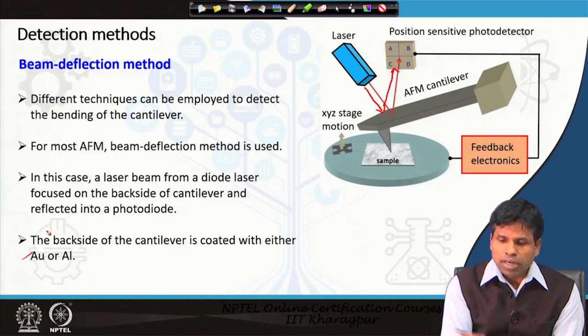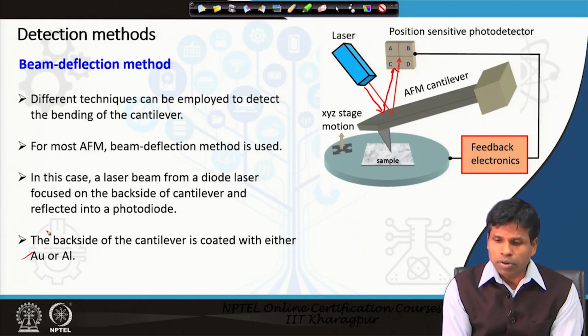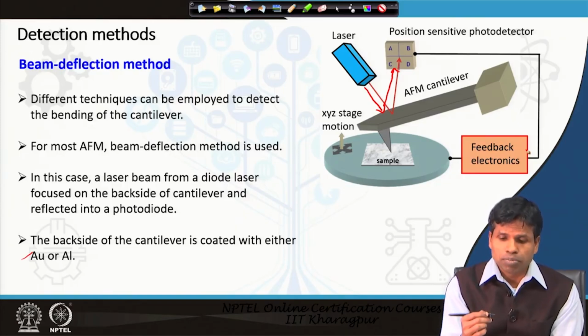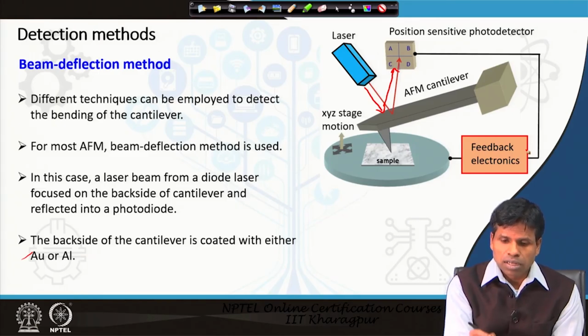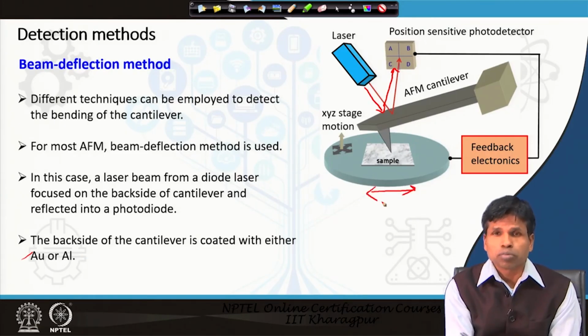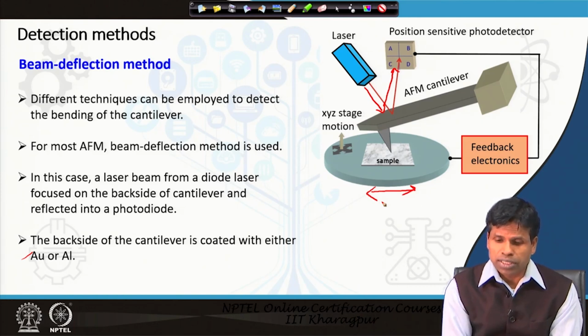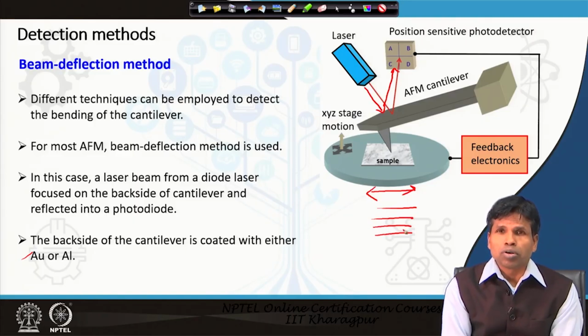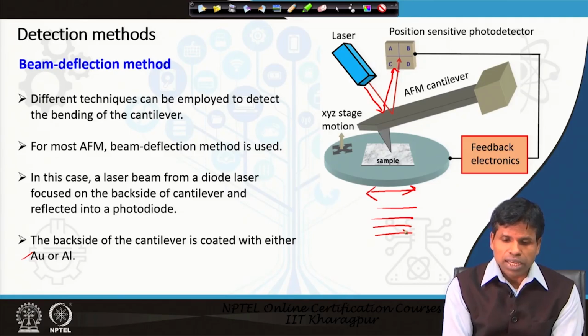After the position sensitive detector detects the position of the cantilever, it gives the information to the feedback electronics, which will note the position of the cantilever, or how much the cantilever deflected upwards. And we have a stage motion in the xy direction. The sample stage will keep moving in the xy direction. At every place of the sample, we scan a particular region and get a surface topography.